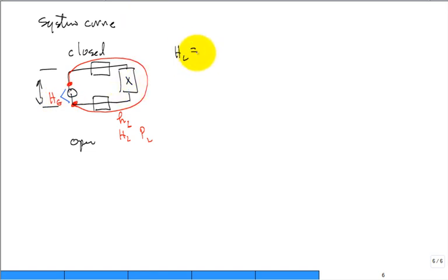Well, we know how to model that, pumping systems, right? Be like some f L over D, 1 half V squared, plus what else? Sum of some loss coefficients. If I start changing valve positions, K could go up if I close the valve, or down. Or if I have elbows and T's and other things, times 1/2 V squared. Does this look all good?